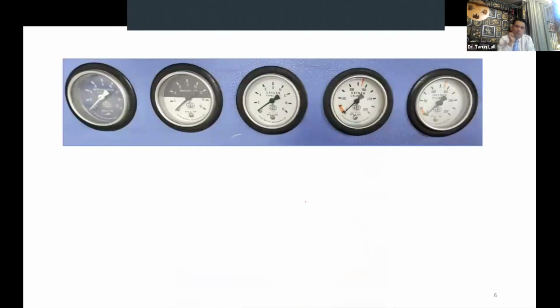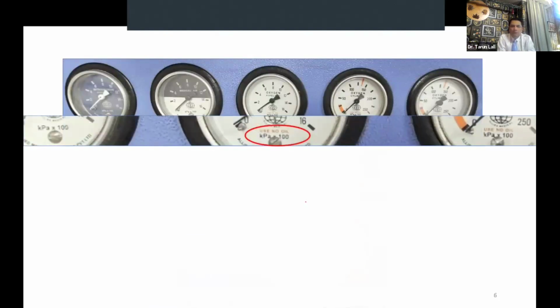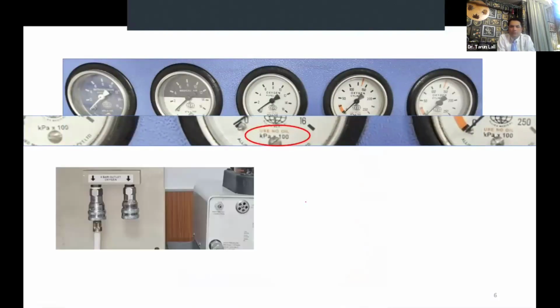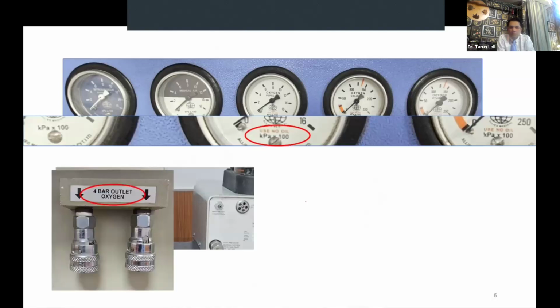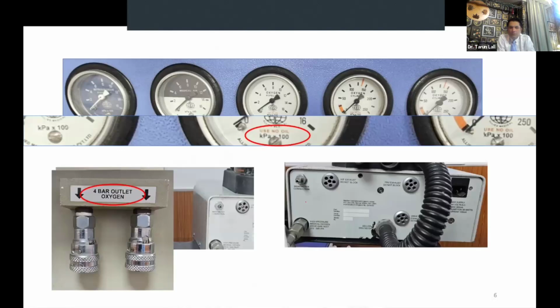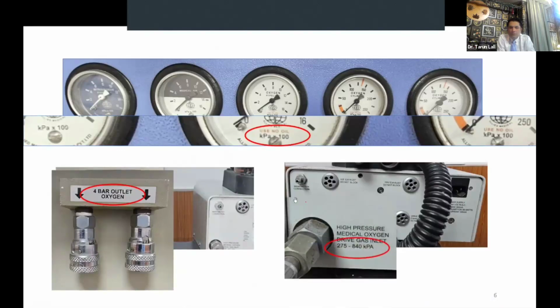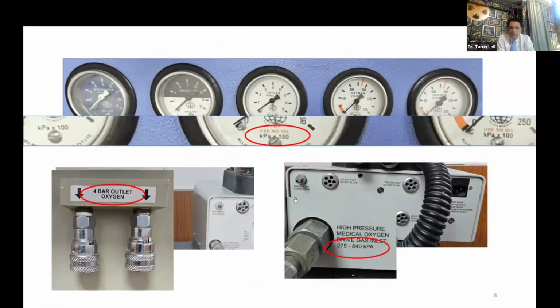On the pressure gauges, we see 100 kPa is used. Where they have an outlet for oxygen, they have used 4 bar. And on the ventilator, it again comes back to 275 to 840 kPa. Now, if you are an anesthetist and you only remember in PSI and you know that your pipeline is giving 40 to 60 PSI, when you come across this machine suddenly in the morning, you will have problems.